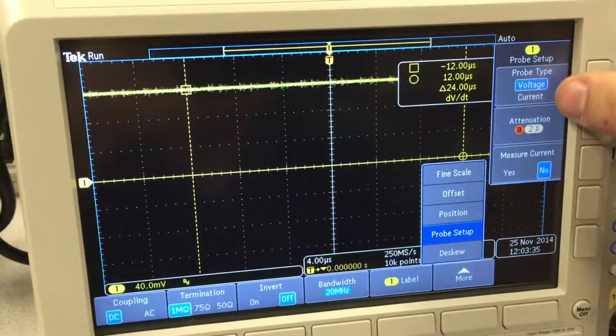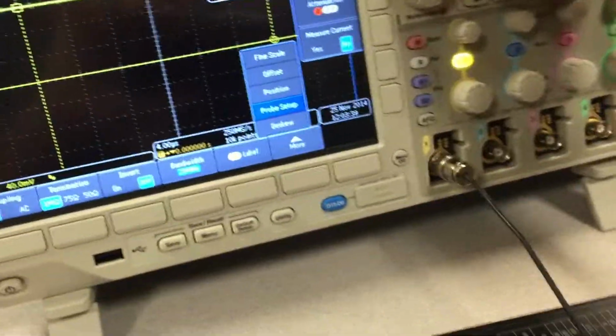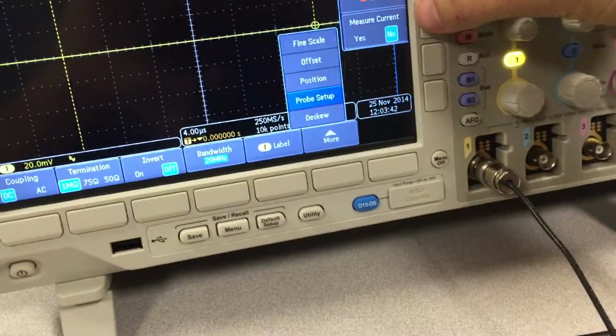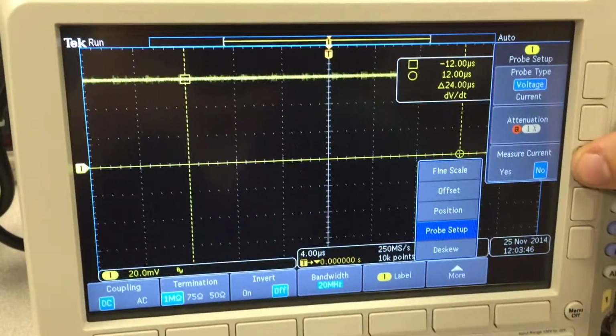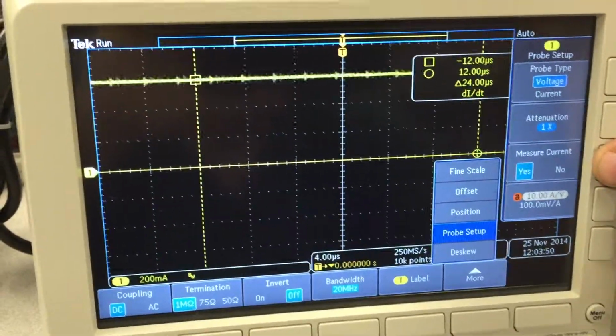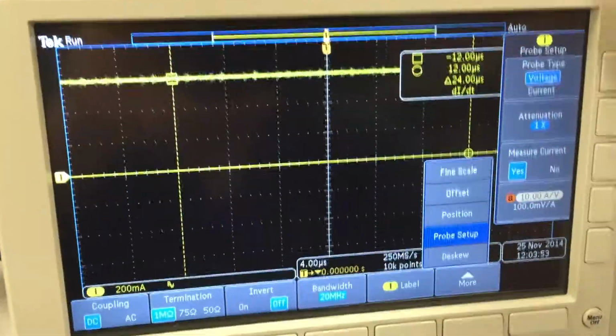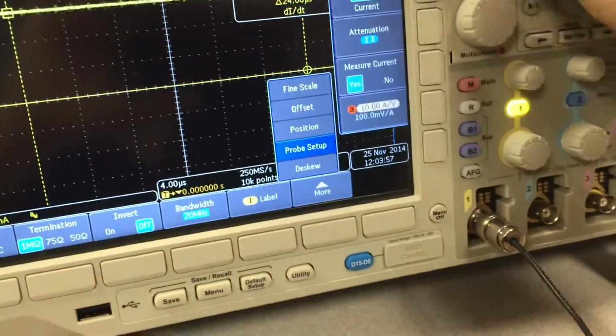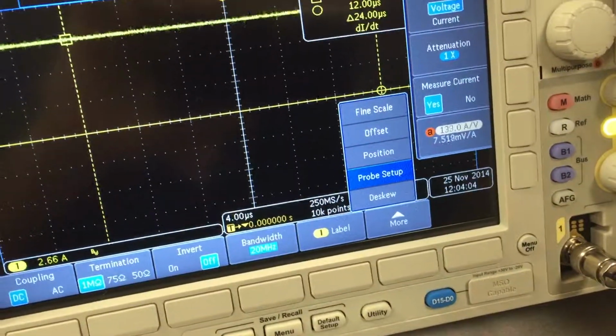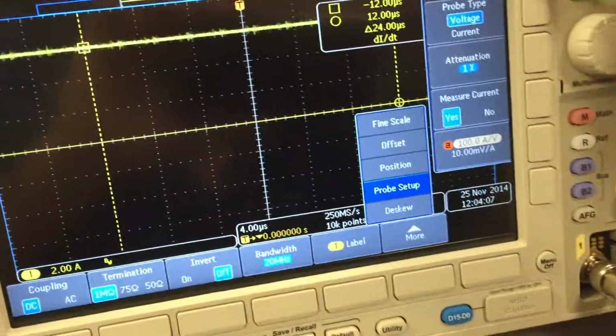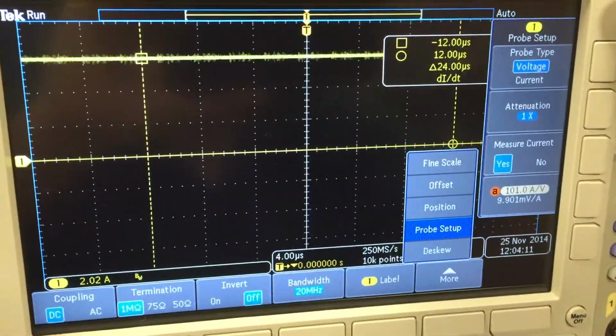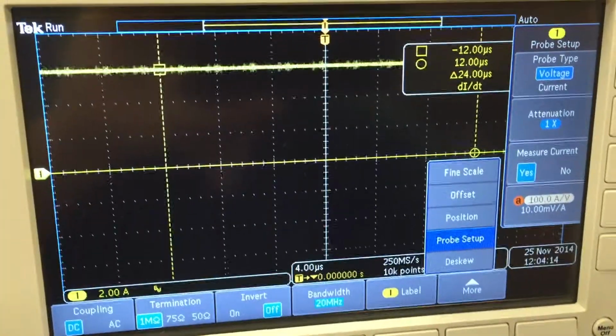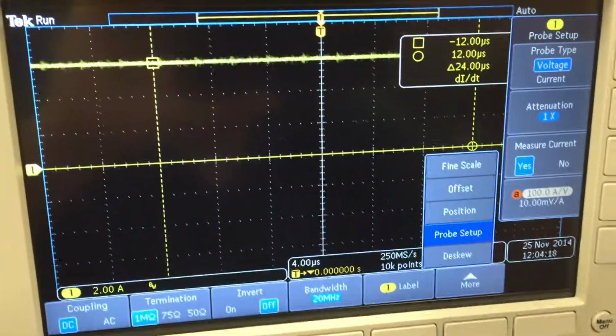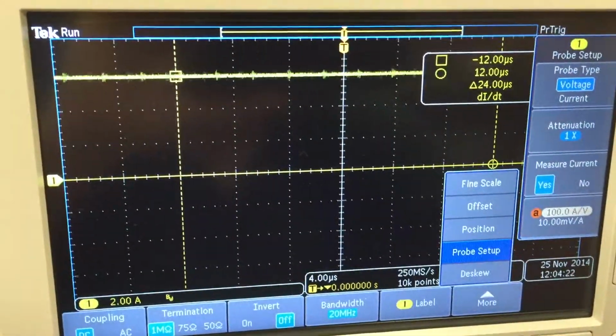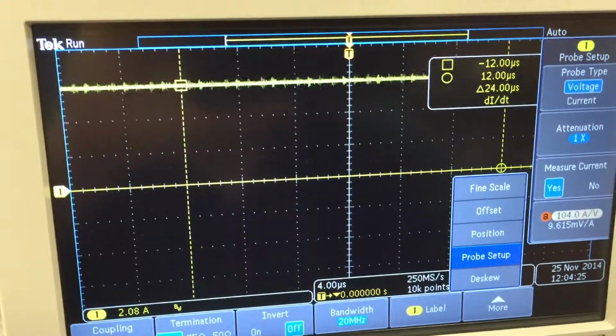tell this we want to use this probe as a voltage probe, but to measure current. And we have to tell it how many millivolts per amp this probe sensitivity is, or how many amps per volt. And we can express that here to say this probe is roughly about, our two steps are either 101 amps per volt or 100. So 9.615 is much closer to 10 millivolts per amp than it is, we could leave it. It's about halfway in between.